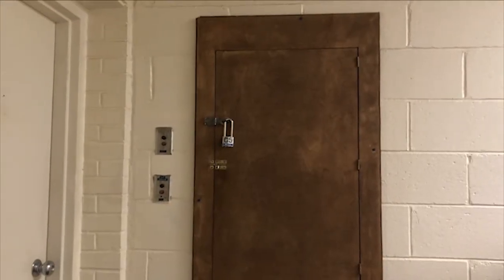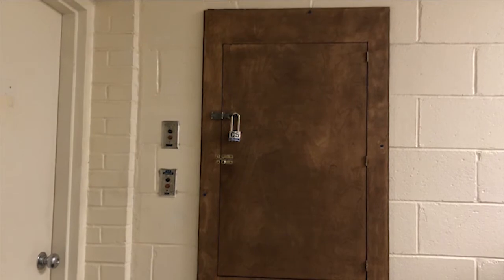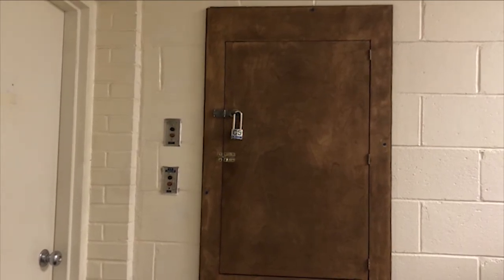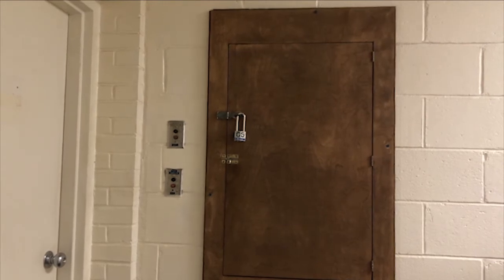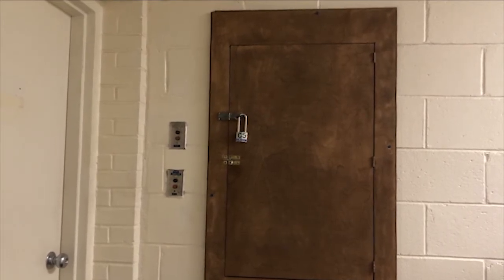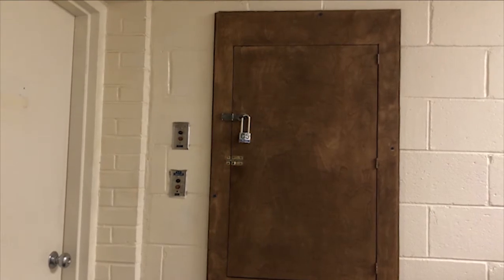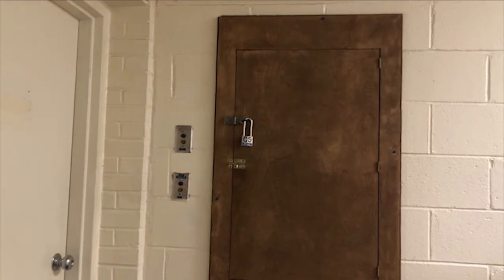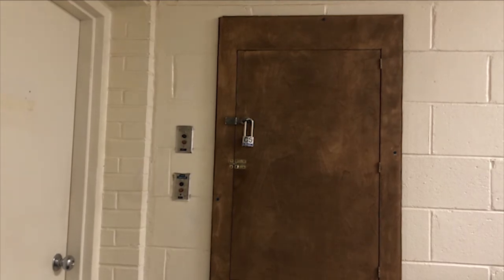I found it. Here's the breaker box. The only thing is, it is so far away from where we're going to be setting up the truck that it could be problematic, because the attenuation, or the power loss, over that long a piece of cable is going to be tremendous. So in this case, instead of trying to run 3-phase cam lock cables from here out to the other side of the building, let's just go ahead and arrange for a generator, or a Jenny as it's sometimes called. Make sure it can handle the 100 amps plus, because you'll always want some headroom.